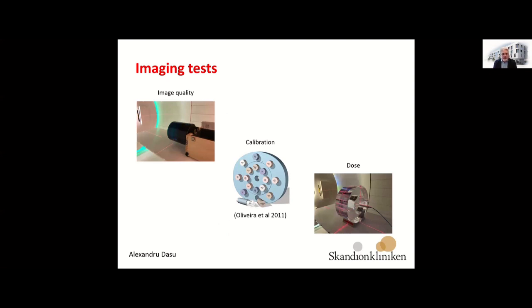If we're talking about imaging tests, what you have to check is the image quality, the contrast, the resolution that could be achieved, the noise in your image, and the calibration. This is especially important for proton therapy, where the predicted range of the proton is very much dependent on the Hounsfield unit calibration of the machine. If you're talking about CT, you also check the delivered dose from the imaging modality, not least for the cone beam CT, which gives a significantly higher dose in comparison to planar imaging.